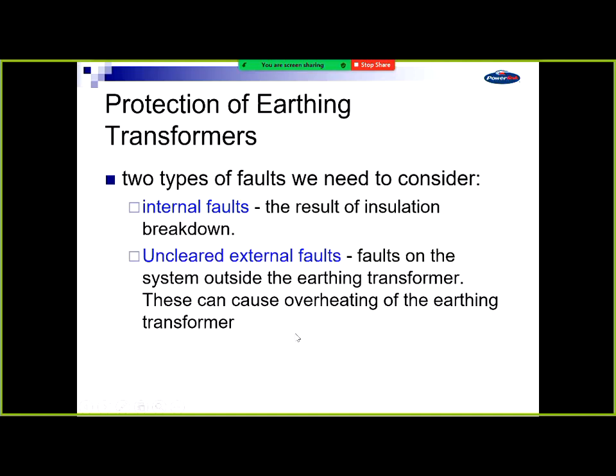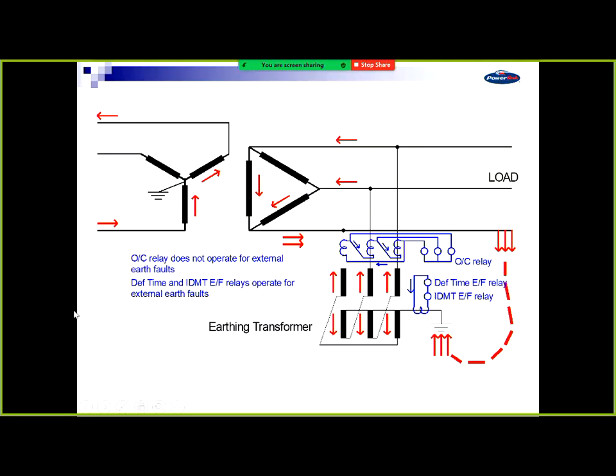There are 2 types of things we need to consider when protecting earthing transformers: the internal faults, and the uncleared external faults. So that's the arrangement that you've got. A star delta transformer on the left-hand side. You see the earthing transformer. It's also called a zigzag transformer. That's another common name for this type of transformer. So if you've got your load on the right-hand side, this would be the typical 132, 22 kV transformers that we've got. They range in size from about 20 to 50 MVA.